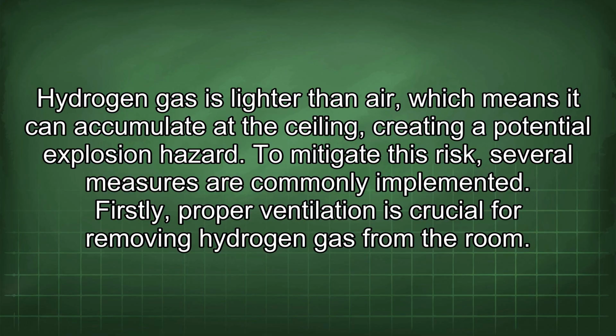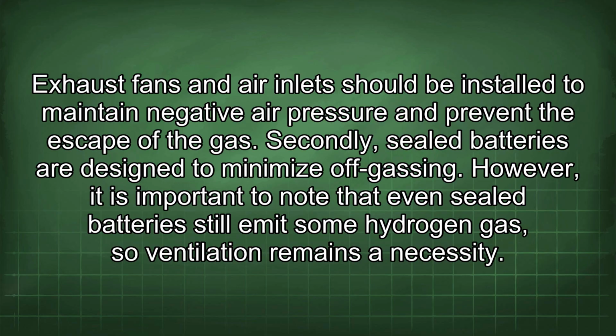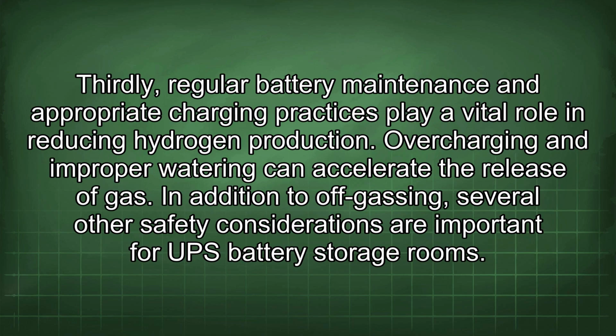To mitigate this risk, several measures are commonly implemented. Firstly, proper ventilation is crucial for removing hydrogen gas from the room. Exhaust fans and air inlets should be installed to maintain negative air pressure and prevent the escape of the gas. Secondly, sealed batteries are designed to minimize off-gassing. However, it is important to note that even sealed batteries still emit some hydrogen gas, so ventilation remains a necessity. Thirdly, regular battery maintenance and appropriate charging practices play a vital role in reducing hydrogen production. Overcharging and improper watering can accelerate the release of gas.